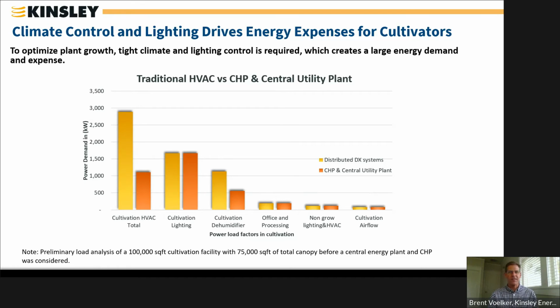When the utility loses power, the CHP automatically shifts into emergency mode. It's called islanding, and it begins to operate the facility independently without interruption of power. When the utility comes back, the CHP switches back, the main utility breaker closes, and the CHP switches to parallel and cooperate again with the utility. So in this way, we've got the best of all worlds. We've got the high efficiency of CHP and the resiliency of a backup power system, as well as utility power to handle transients. So with that, I'll pass it over to Steve, and he'll take it from here.